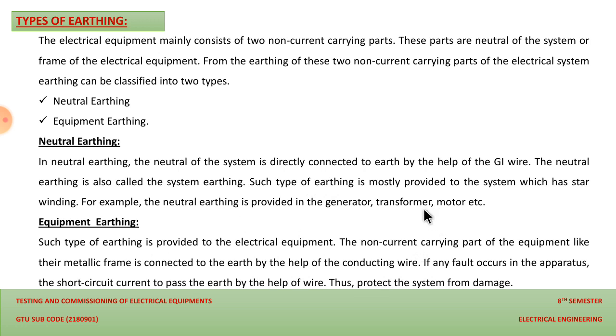If any fault occurs in the apparatus in the premises, the short circuit current passes to the earth through the wire provided on the body of the equipment. Thus protection can be provided, and we can save the equipment from damage. And suppose a person comes into contact with that faulty equipment, then we can save that person's life through both neutral earthing and equipment earthing. So these are the types of earthing.